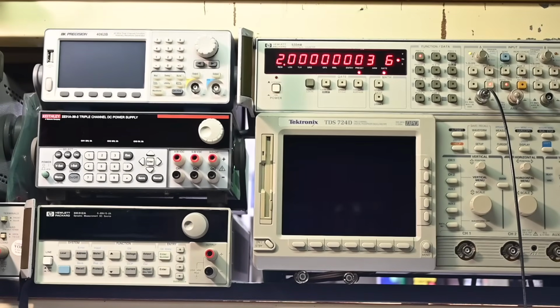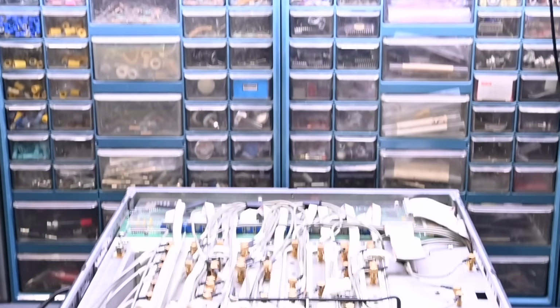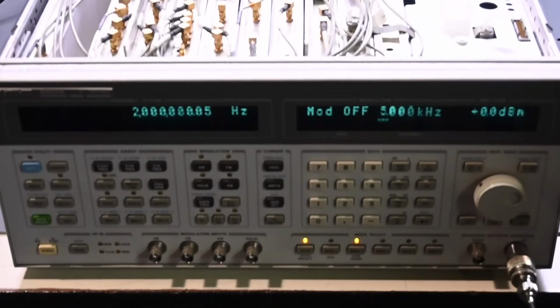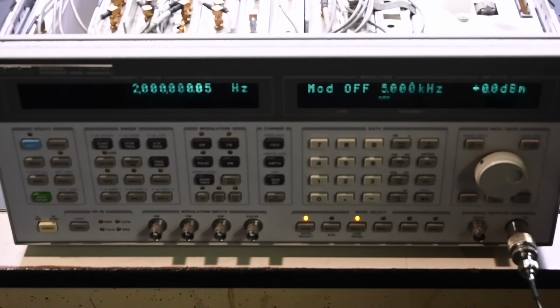And take a look. So it's sitting right very, very close to the same value. So it's just about 10 millihertz off. We have a 0.04, and there's 0.05, so spot on right there, but very, very close. And again, the oven light just turned off, so looks very good at this point. Very happy with that result. Looks like the accuracy for the frequency has returned to what it should be. So I'm going to go back down again to the signal generator right here.